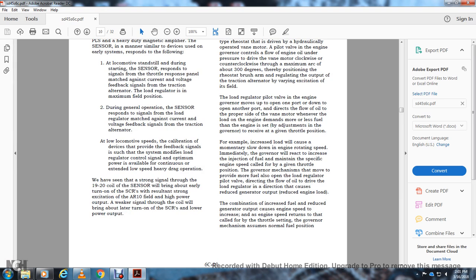For example, an increased load would cause a momentary slowdown of the engine's rotating speed, and immediately the governor will react to increase the injected fuel to maintain the specific engine speed called for by the given throttle position. The governor mechanism's move to provide more fuel also opens the load regulator pilot valve, directing the flow of oil to drive the load regulator in the direction that causes reduced generator output, reduced engine load.